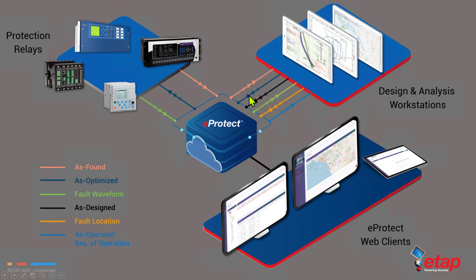as-optimized settings. We can then also retrieve the waveforms, or the fault waveforms, from the relays, RTUs, DFRs, and store the events and the disturbance records inside eProtect and pass those to the design and analysis workstations for further investigation and forensic analysis. The fault waveform that is brought into the design and analysis workstations is then used for fault location. Once the exact or accurate fault location is determined, it is then sent back and saved in eProtect along with the event. So for every event and disturbance record, you know exactly where the fault was located with respect to the electrical model or the single line diagram or the geospatial representation of the electrical system.